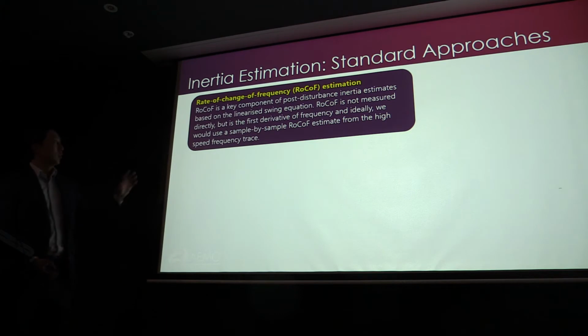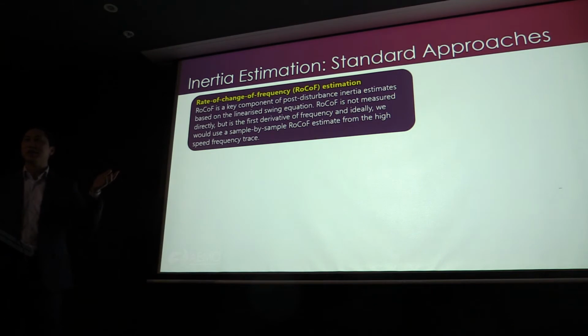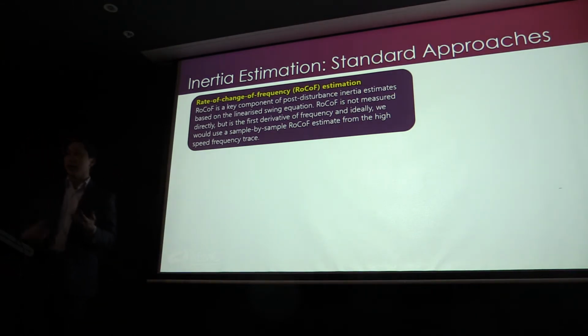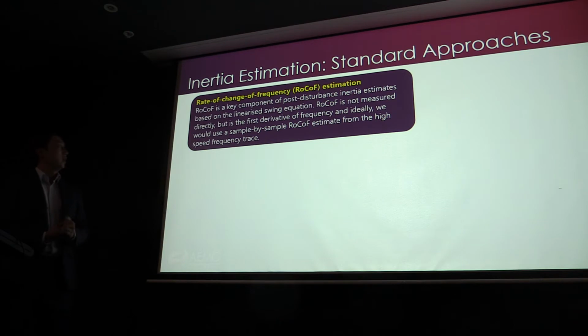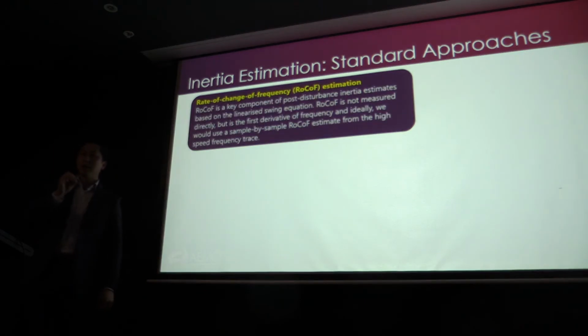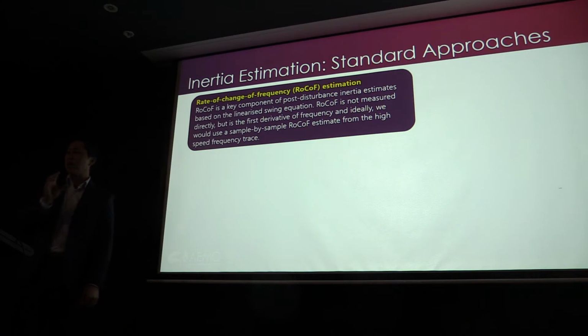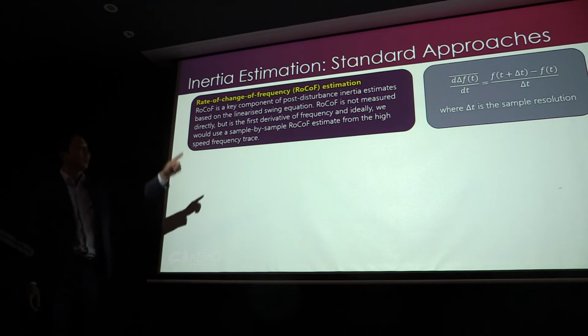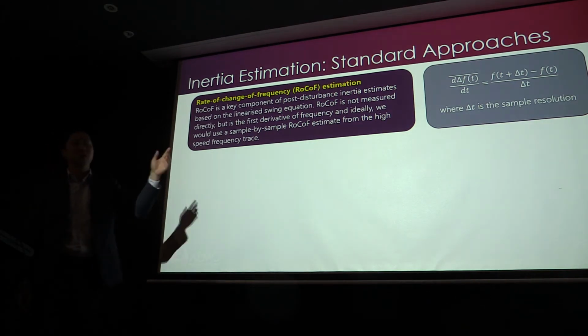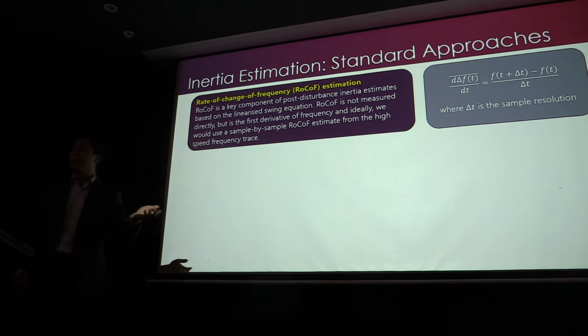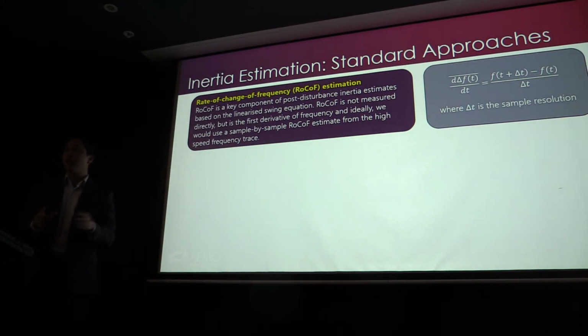So one of the first things I want to point out is that the rate of change of frequency needs to be estimated. It's a very key component. You can't actually measure the rate of change of frequency, because it's the first derivative of frequency, and all you're measuring is frequency itself. Ideally, we would take the high-speed frequency measurement and take a sample-by-sample rate of change of frequency, which would be like taking one sample, subtracting it from the previous sample and dividing it by the sample resolution. That would be the most ideal way of doing the RoCoF measurement or estimation.